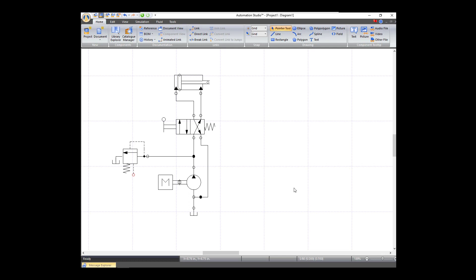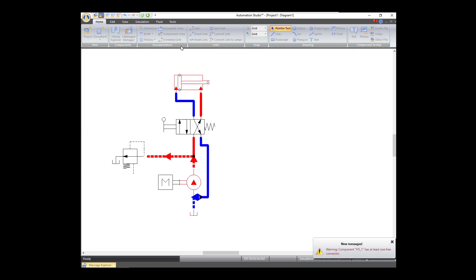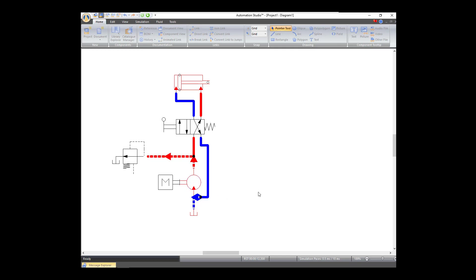Now that it's built, let's go in and simulate it to see if everything is hooked up properly. We can go to Simulation or just use the icon at the top. We have pressure — red is pressure and blue is return. Right now we have a pump, and this is an incompressible fluid. Unlike pneumatics which uses compressible air, hydraulics must use relief valves. Since this valve is closed, the pump — being incompressible — has to keep pushing fluid out through the relief valve.